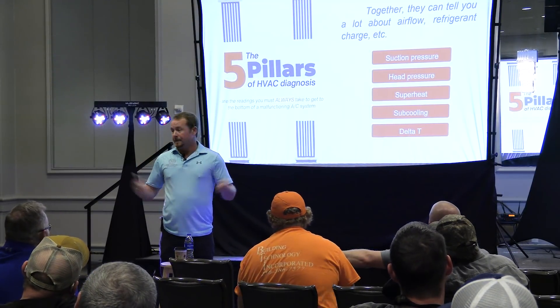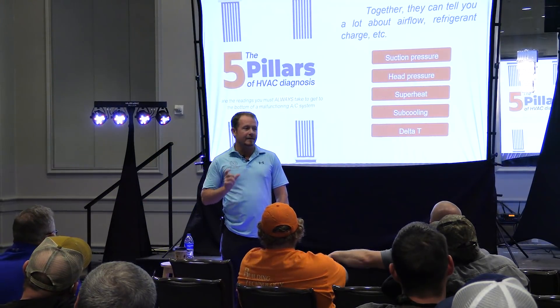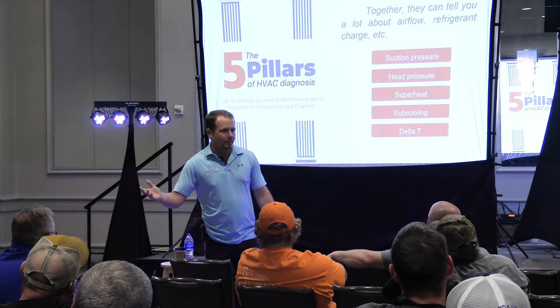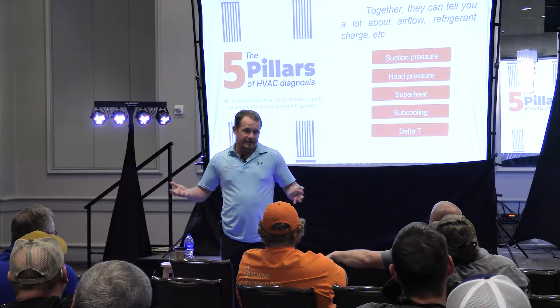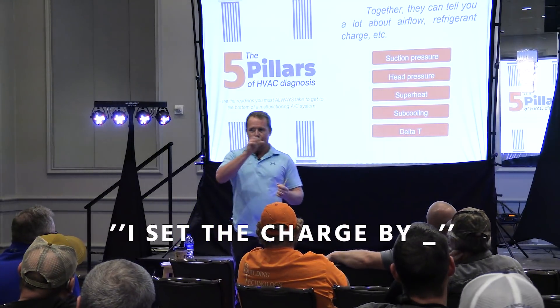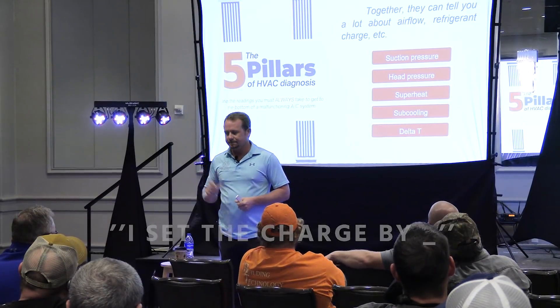A lot of guys would say some version of 'charge is good.' How do you know the charge is good? Because the subcooling is 10 or 12 or 8 or whatever, right? Well, just because you hit a particular number on subcooling doesn't mean the charge is good, because we don't know if there's some other problem with the equipment. You could have a severe restriction in a liquid line dryer and still hit 10 degrees subcooling before the dryer, and the system not be working properly. You could have a metering device that's significantly overfeeding or underfeeding. You can't just use a single number — that's what I was trying to get people to move away from.